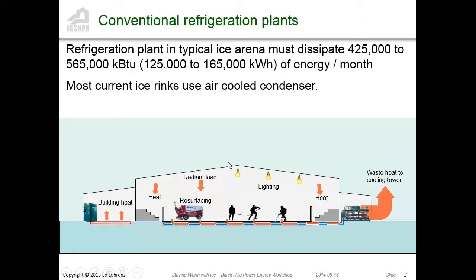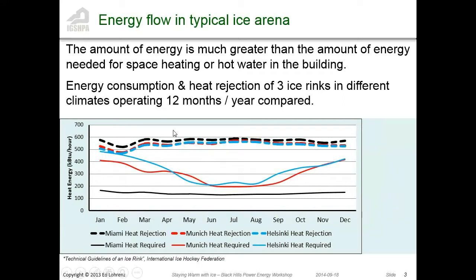Looking at this chart, basically in Miami or in Munich or in Helsinki, refrigeration loads, or the amount of heat that's required, are roughly similar. In Miami, obviously, you don't need a whole lot, except there's a surprising amount of hot water used in ice rinks. Typically, you use water at about 140 or 150 degrees to flood the ice, simply so it bonds better and to get rid of the oxygen from the water, so it makes harder ice. But the refrigeration loads, the heat rejection, are going to be similar in most places. Roughly about 2 million kilowatt hours worth of energy per year.